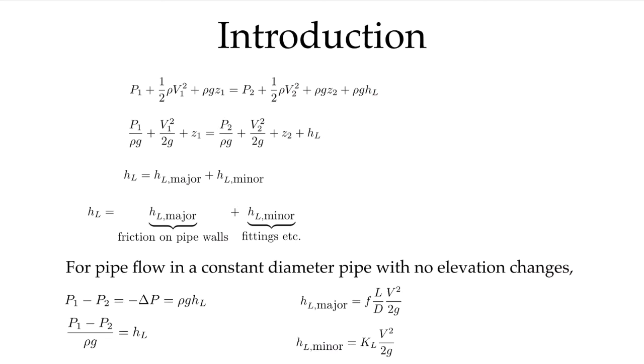We're going to take into account in this case both the major and the minor losses. The major losses are given by the friction factors for the fully developed flow in our straight piping sections, and the minor losses are due to those additions to our piping system: the fittings, the elbows, the valves, and so on.